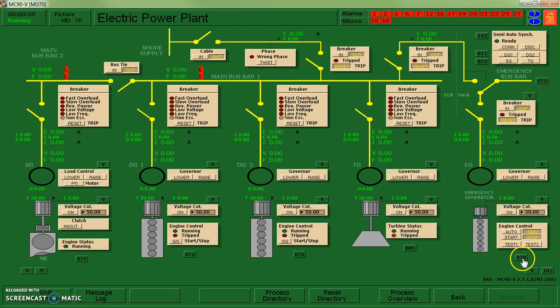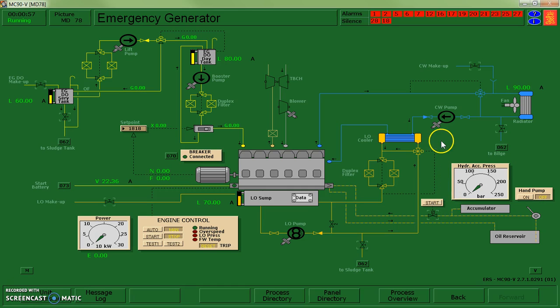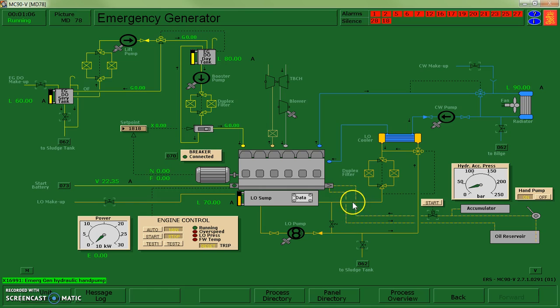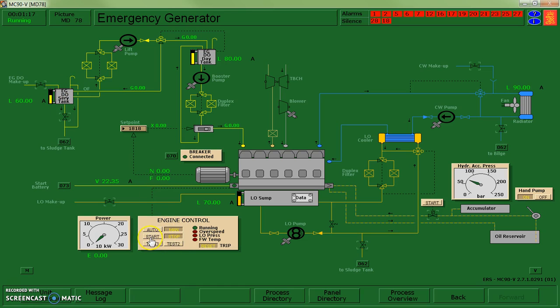If I just go to page 78, what I can do is take a look. I'm going to turn on the hand pump to build a bit of pressure for my lube oil system. Everything appears to be ready to go. I've got diesel oil. Let me just start it.